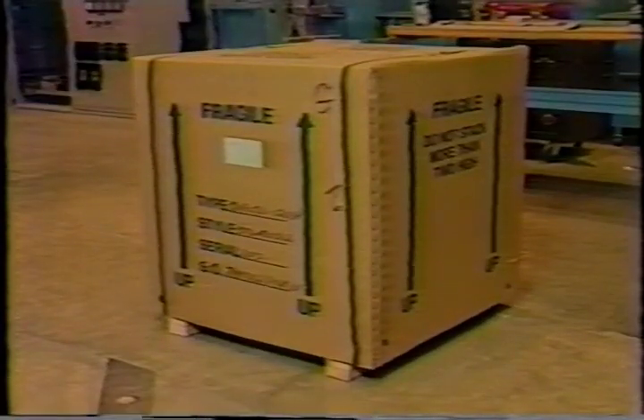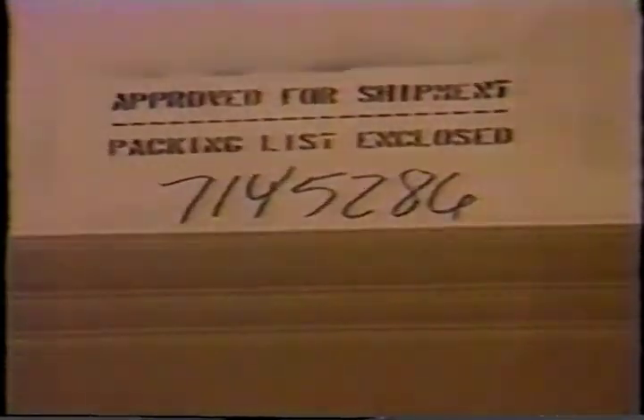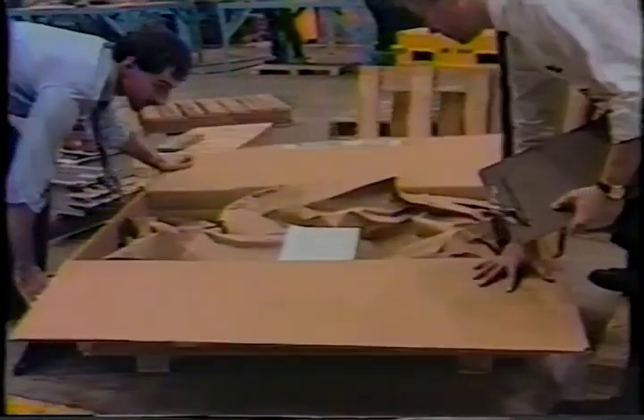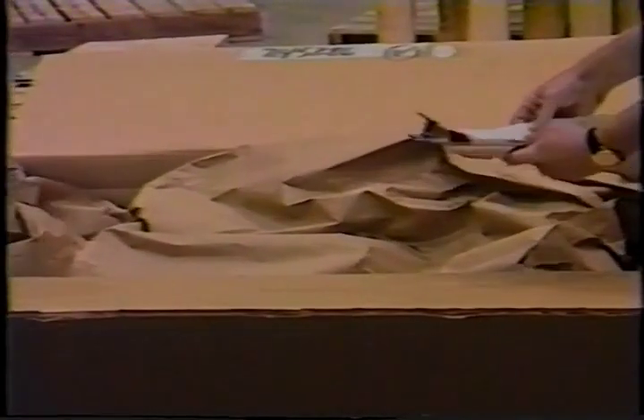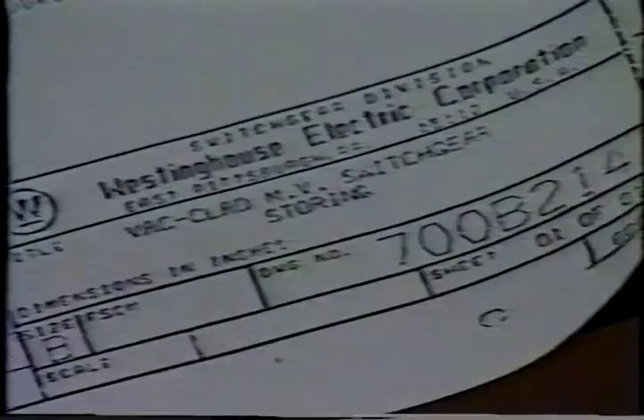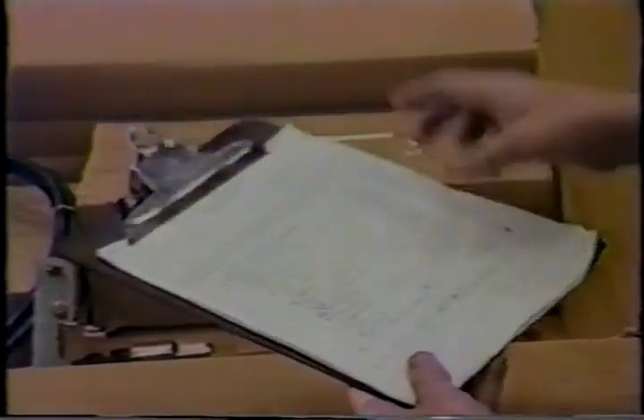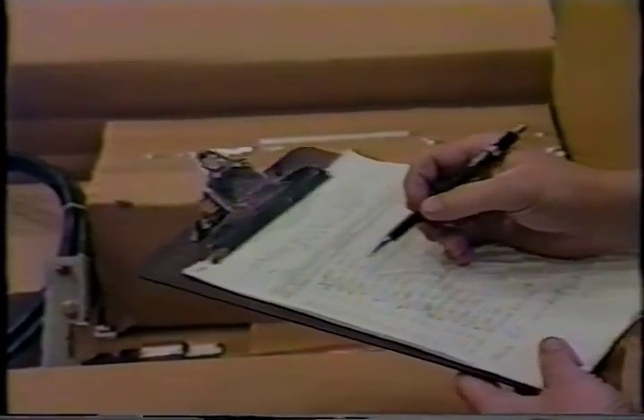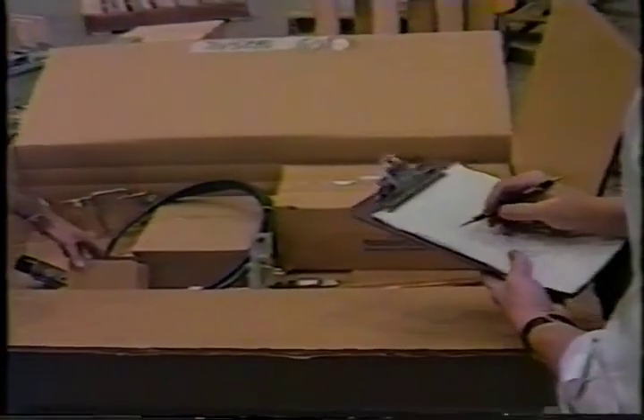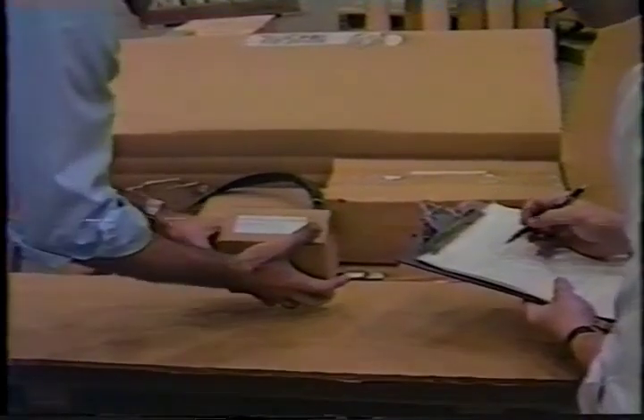The breakers are shipped in individual containers. Each switchgear group and all the cartons and crates are labeled with a shop order number and a shipping weight. In the cardboard accessory box, there will be a shipping packet containing the shipping lists, storage, and handling drawings. When the switchgear arrives at the installation site, check it to make sure all parts described on the shipping list have been received. Do this before discarding the packing material.